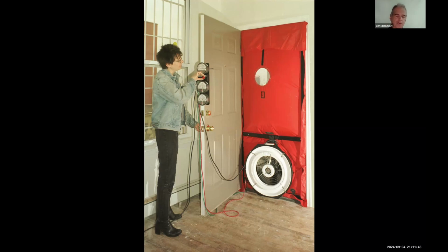So it measures the pressure difference. Back in the day we did it at 25, 50, and 75 pascals. Now you would just measure it at 50. Another one of those needles reads pressure difference, and another scale on the same gauge computes cubic feet per minute, air volume flow. We usually pull negative on the house, but some of the testing protocols say go negative and positive. It usually doesn't read very different.